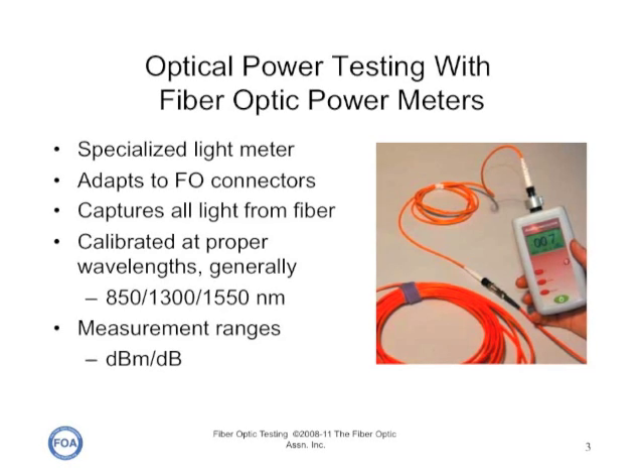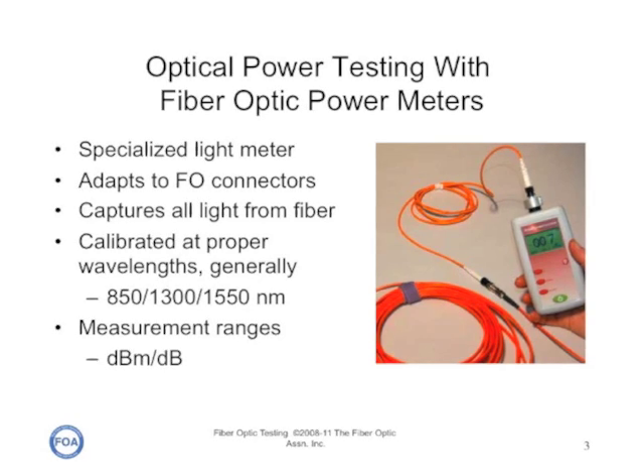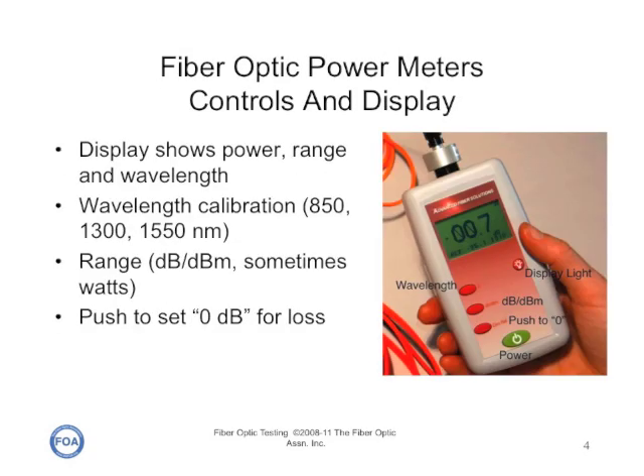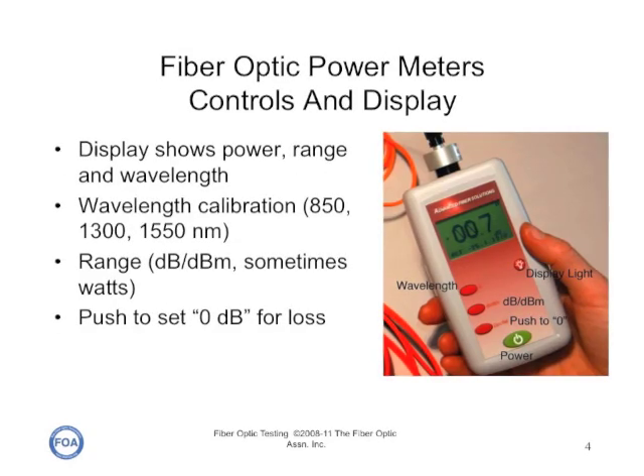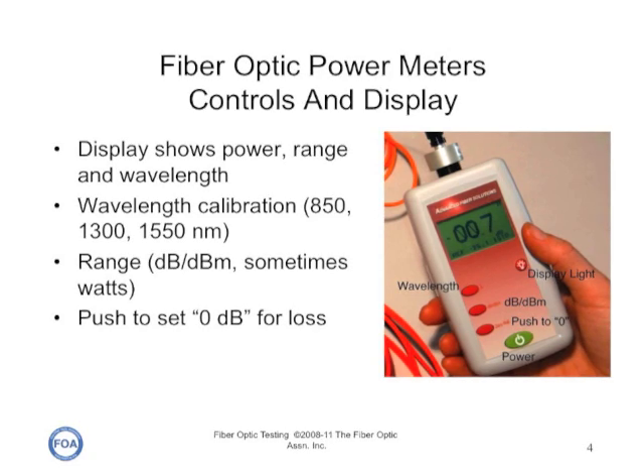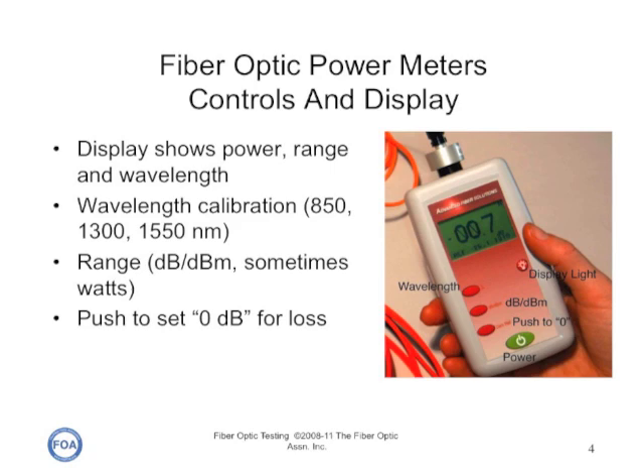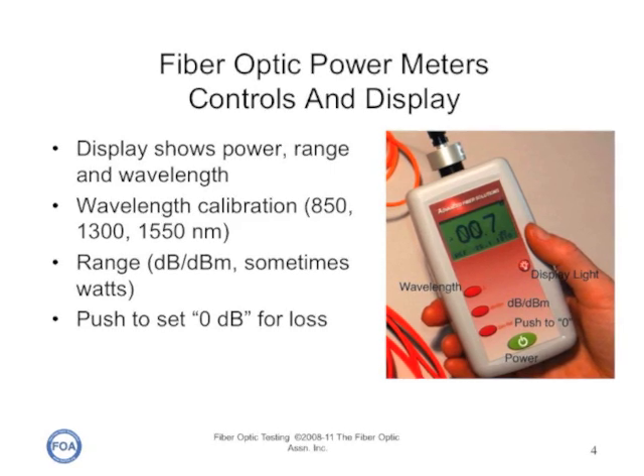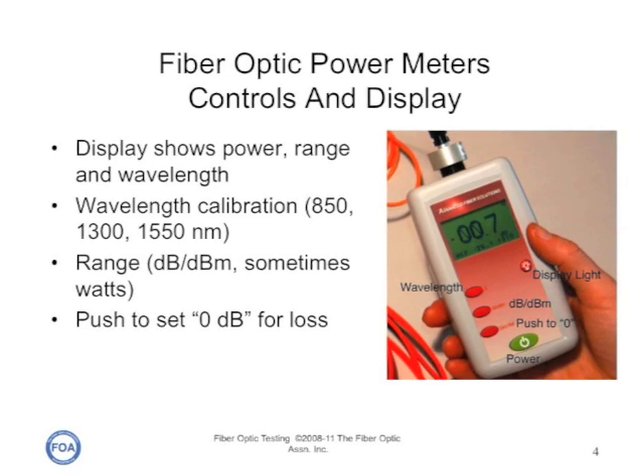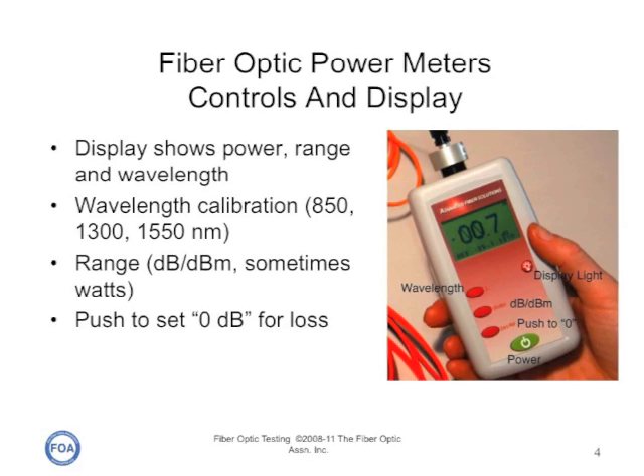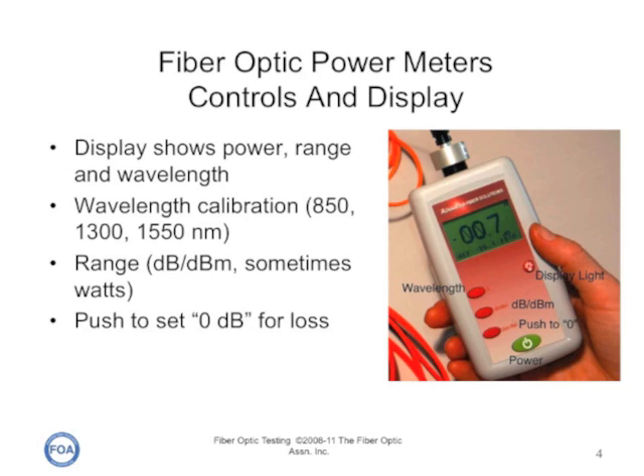Most power meters measure in both dBm and dB, and we'll explain what that means shortly. Our meter has a digital display that shows the output power from the fiber, the range of the measurement, and the wavelength. The wavelength calibration is done at 850, 1300, and 1550 nanometers — the wavelengths that international standards groups have agreed upon. The range is in dB or dBm, and sometimes in linear scales in watts.